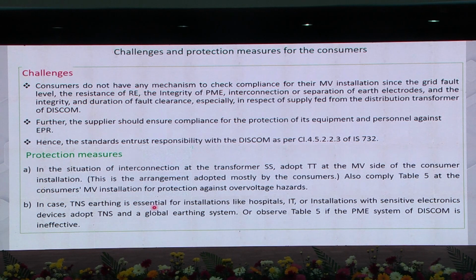Then another thing is, in case of TN-S earthing, it is essential for installations like hospitals, IT, computer industries, as well as industrial places where sensitive electronic equipment is involved. You must have TN-S. So, what we have to do is adopt a global earthing system. If you observe a global earthing system, you don't bother. If there is no feasibility to connect the rebar earth or foundation earthing and other things, you should observe table 5, which is very tough. So, global earthing is becoming an essential factor in the case of installations involving the necessary TN-S earthing system. Observation of table 5 is not at all required if you go for global.